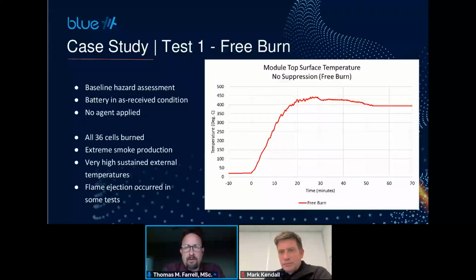We put the battery into thermal runaway, and with every cell that failed, it added to that temperature, and it just got hotter and hotter until the surface was absolutely cooking. We applied no agent to this. All 36 of the cells inside that module burned. The amount of smoke that came off this test was really excessive. It overwhelmed our 20,000 CFM blower hood that we were using to extract fumes from that room and clean them before sending them into the atmosphere.